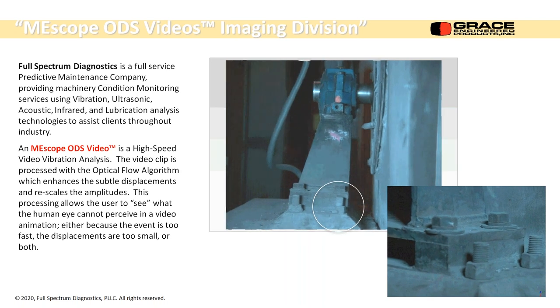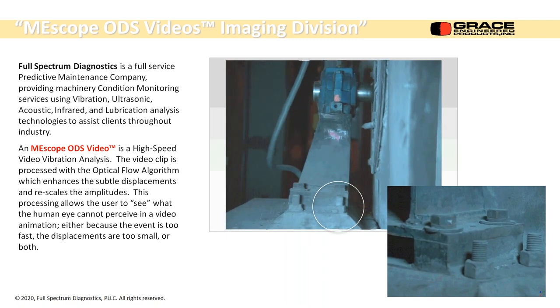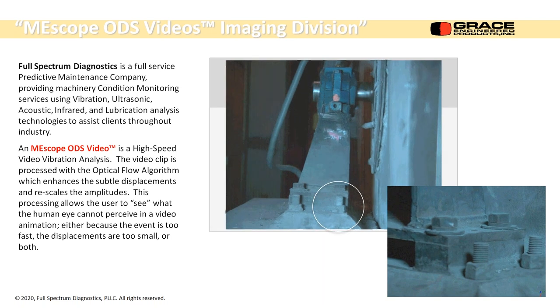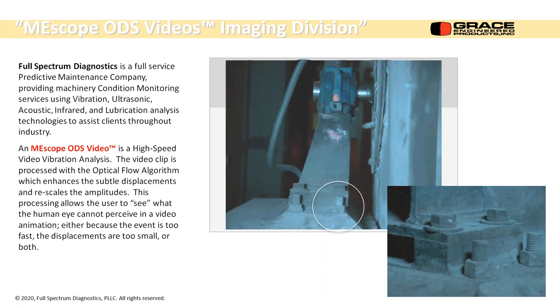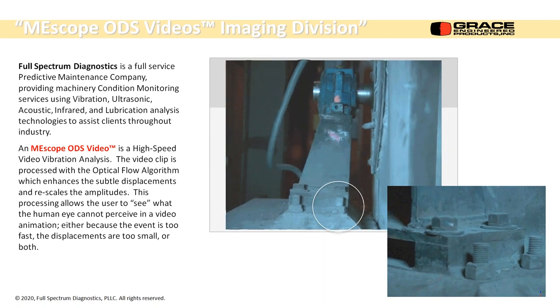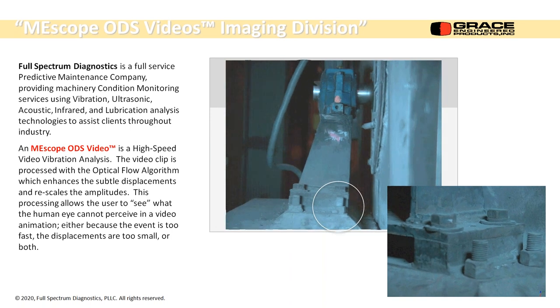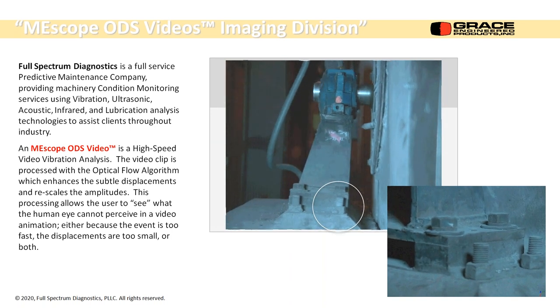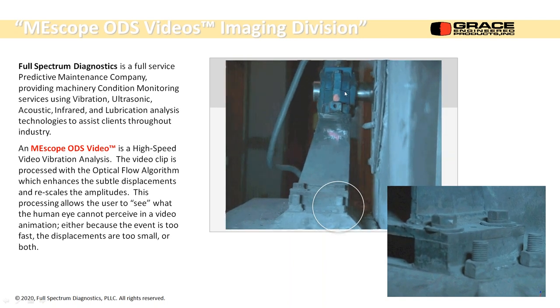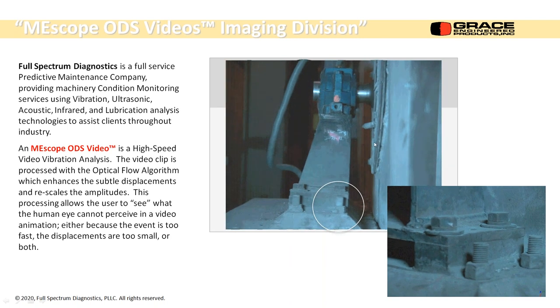And this is a bearing housing on a fan. Outboard bearing, you can see how it's moving. And this is real life. It's amplified, obviously, but they had all kinds of problems with this thing. And they were always looking at the top where the bolted section for the bearing is, and that's always been tight, and they've over-tightened it and caused other problems.